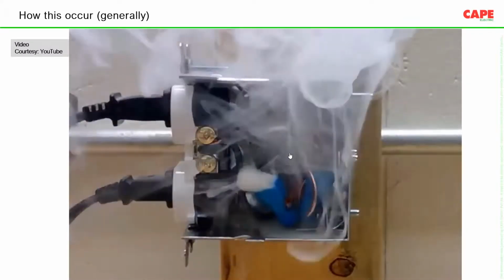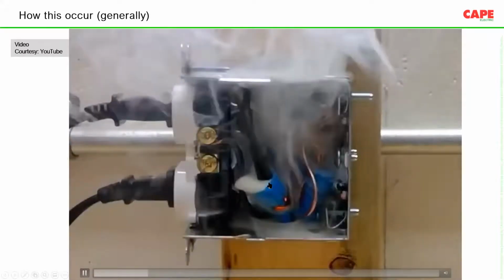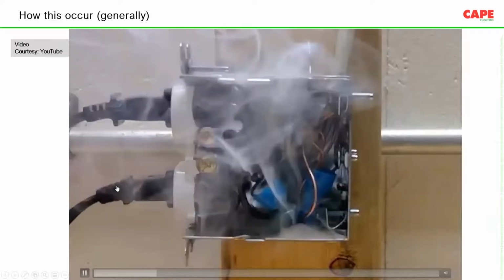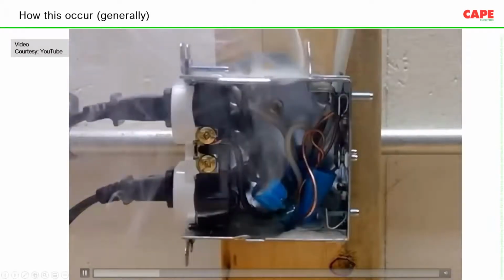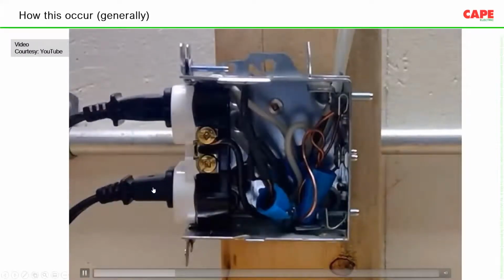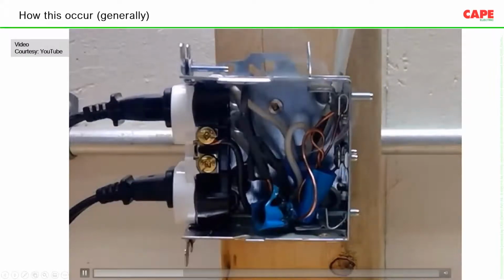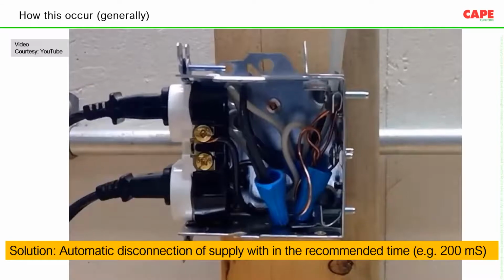Now the problem we can assess in two ways. The first problem is an insulation failure, but the actual fire is created by the source. If the source is not strong enough to dissipate this much energy, there is no fire. So the fire is ignited because of the source. Source classification is very important with respect to creating fire. Sources are classified into three: power source 1, 2, 3. Power source 1 means a source which is able to disconnect your system within 3 seconds. Most of our electrical or air conditioner-like appliances are able to withstand an internally created fire up to 3 seconds. But when you install the air conditioner in your wiring, you must ensure that the disconnection is happening within 3 seconds. So there the power supply classification happens.